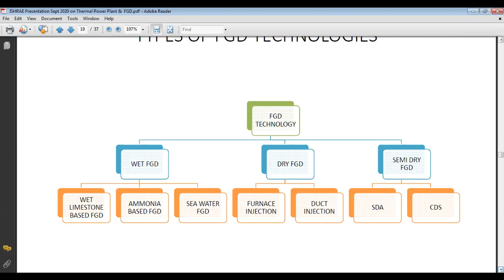The wet FGD is further classified in three categories based on the type of reagent: limestone based FGD, ammonia based FGD, and seawater FGD. Dry FGD is further classified based on the location of injection of the reagent or sorbent. If it is injected in the furnace, it is called furnace injection, and if we inject in the duct, it is called duct injection. Semi-dry FGD is further classified into SDA and CDS: CDS is circulating dry scrubber technology, and SDA is spray dryer absorber technology.